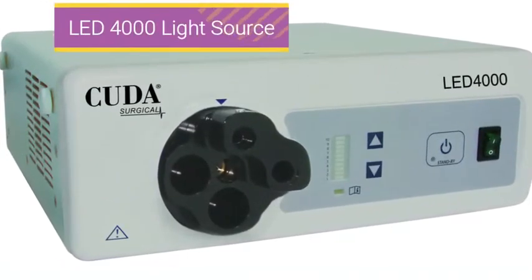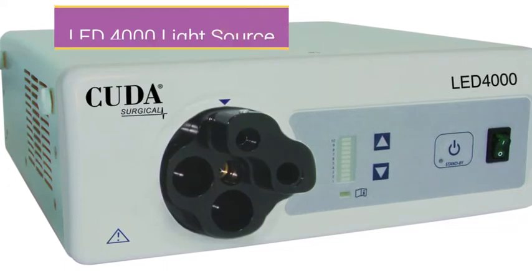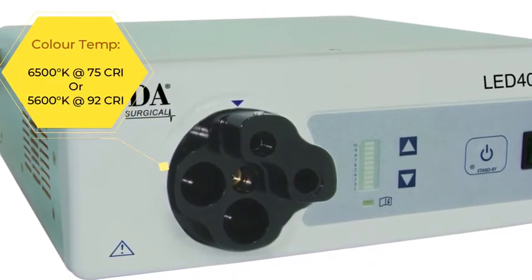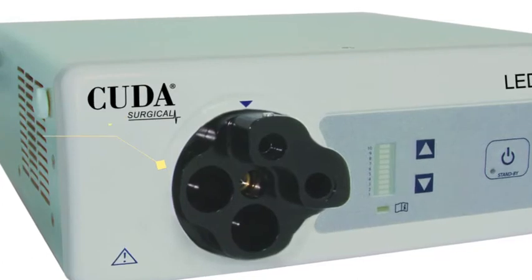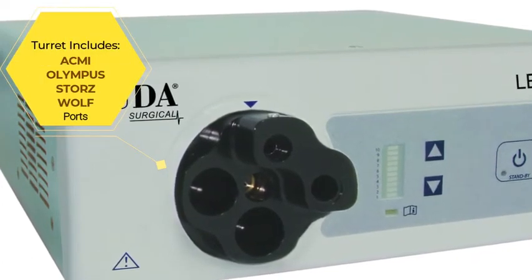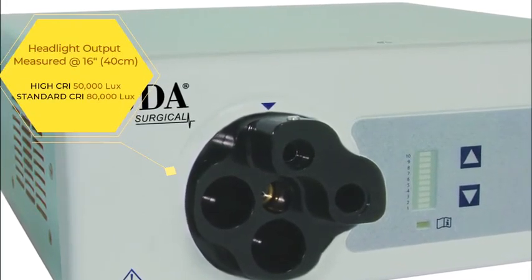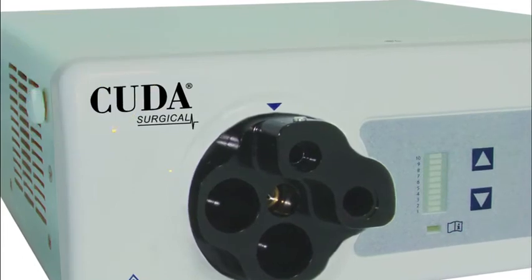The LED 4000 is a state of the art LED light source designed to provide light for headlight and endoscopic procedures. The luminous output is comparable to many Xenon light sources currently being used in endoscopy. The expected LED life of 30,000 hours eliminates the need to purchase replacement lamps, thus saving money in operational cost.